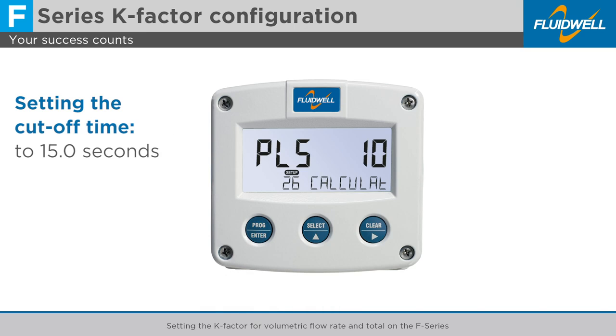The last step is to set the cutoff time in seconds. This is the threshold for a minimum flow. When during the cutoff time no pulses are received, the F-series will show a zero flow. This prevents the F-series to continuously show the last calculated flow rate if there isn't any flow detected.